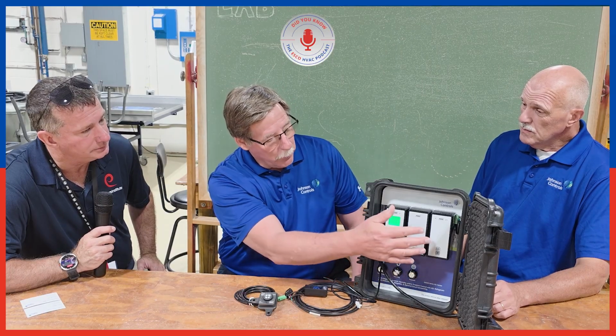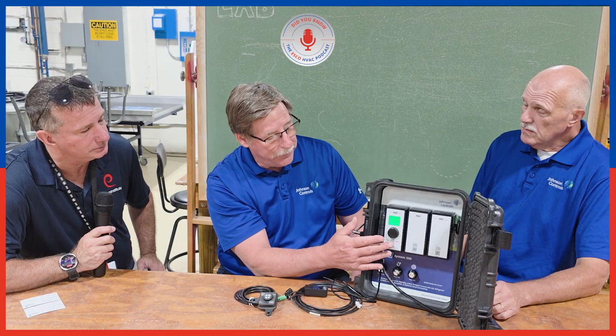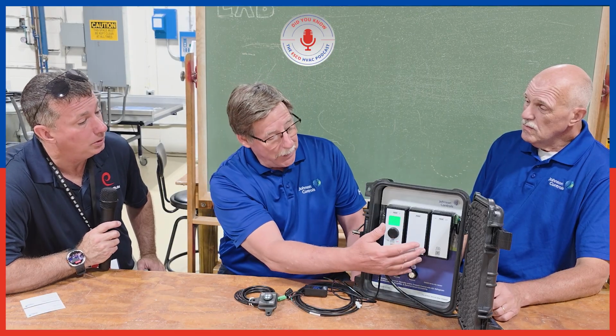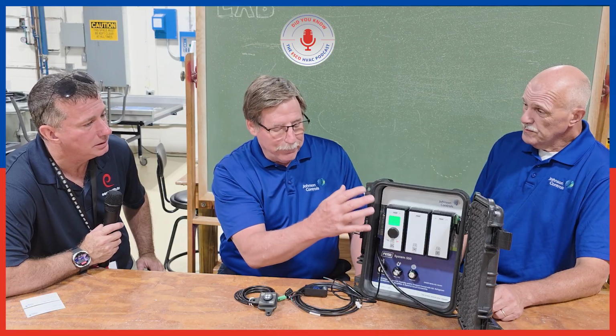And then, we're not using it in this particular application that I have configured, but the last module here is what's called an expansion module. It will provide either 2 more relay outputs, or you can have an expansion module that will provide 2 analog outputs. So you can have a combination of relay and analog outputs up to a total of 10 outputs. But to talk specifically about A2L leak detection and mitigation, this is a full functioning control, meaning that it supports both single and multi-stage with temperature, humidity, and pressure sensor inputs, as well as the full capabilities of A2L leak detection and mitigation.